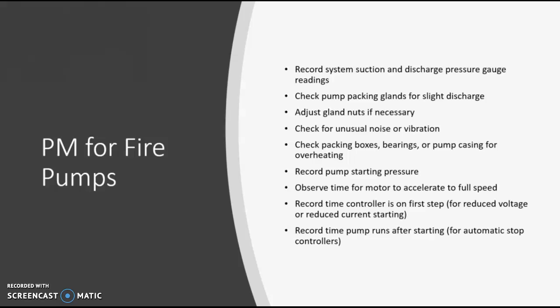Record the system suction and discharge pressure gauge readings. Check pump packing glands. On certain pumps, you've got a rope gasket that will leak the entire time, and make sure that rope gasket's okay, that everything's all right. Check for unusual noise or vibration. Packing boxes, bearings, pump casing for overheating.